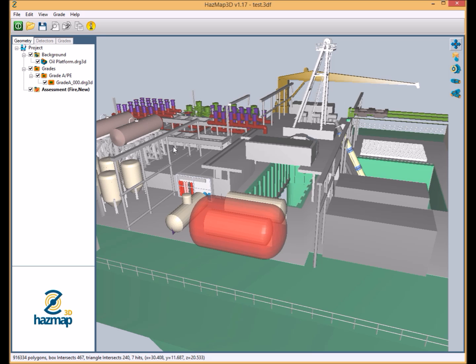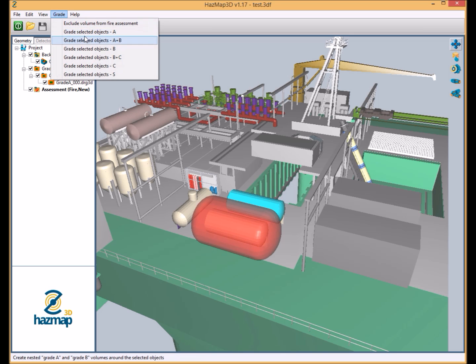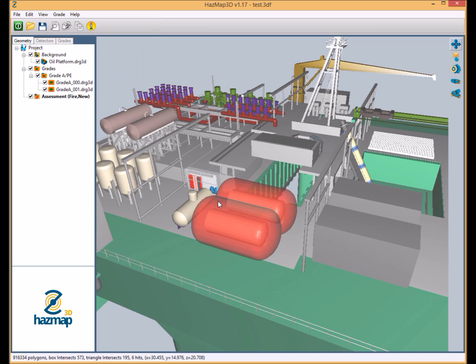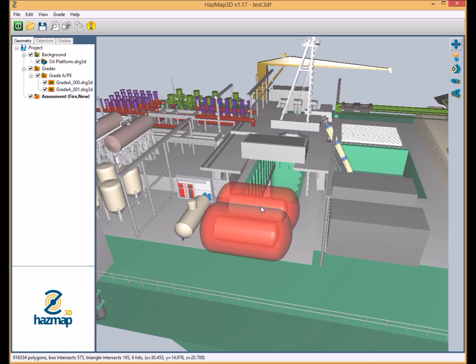We'll add another grade A. Obviously these grades are based on the escalation potential, so if we're in a very high risk area we want to detect a smaller fire size so we can prevent this from escalating to a point where it would become difficult to control and mitigate.